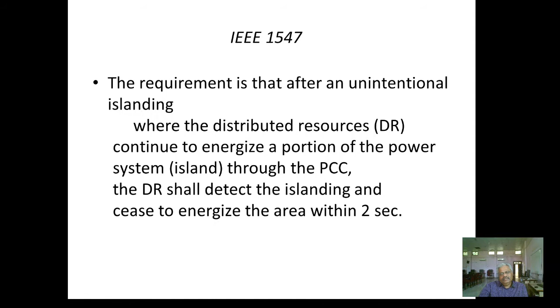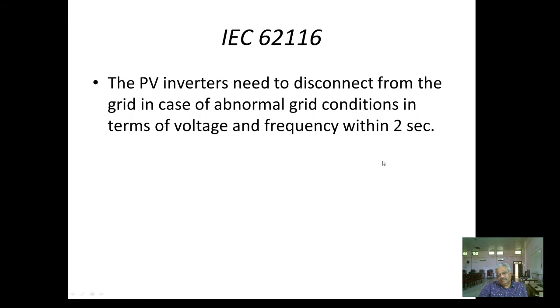This is as per IEEE 1547. IEC 62116 says that the PV inverter needs to disconnect from the grid in case of abnormal grid condition in terms of voltage and frequency within 2 seconds. In the previous case also, this 2 seconds was there, in this case also 2 seconds was there. Therefore, what is the importance of this 2 seconds?